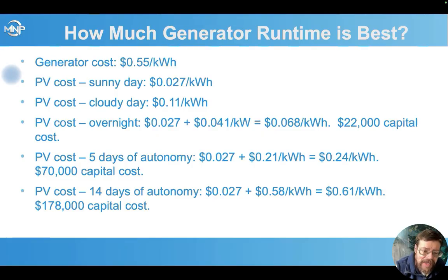So there's a trade-off. Do we want the cheapest power over the full amortized lifespan, or a trade-off between capital costs versus operating costs? So somewhere in there we're going to say, okay, the generator might be more expensive in the really long run, but we just can't afford $178,000 of batteries in this example to give us 2 weeks of full battery storage.